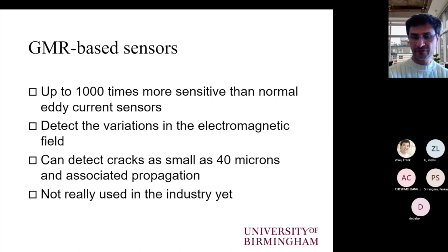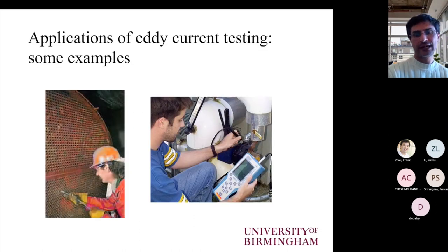So the size of the coil with respect to the defect size are related to the sensitivity of the instrument. Here are some photographs that show examples of eddy current testing. So this on the left-hand side shows the use of eddy current testing for the inspection of tubes in heat exchangers. And on the right-hand side, you can see different components being inspected with a handheld device.